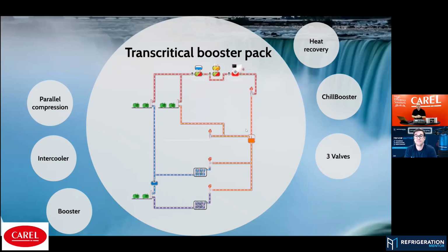Yeah. So this is the process of elimination. To do this, you really have to know what each part is doing, what the job of each single stage is. And yeah, you simply can't go out and say, we have a problem on this side. This has to be this high pressure valve, but you could be wrong. If you don't have an idea why this would be the problem, there could be a broken probe. There could be something else that is the problem. And many people out there are simply going out and exchanging parts, without knowing what they are doing. Sometimes they're right, sometimes they're not. But to be more on the right side, you have to know before you go.